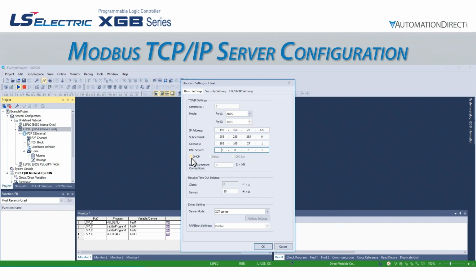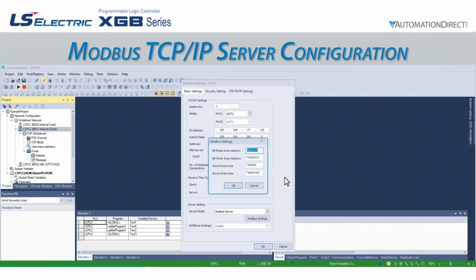If we are using the PLC as a Modbus server, we can go to the Server Mode dropdown and set it to Modbus Server. We also use the Number of Dedicated Connections field to set the number of connections that will be reserved for external Modbus clients with our PLC acting as the server. We will leave this at the default of 3. We can then click the Modbus Settings button, and the Modbus Settings window will open. In this window, we can configure the starting addresses that can be accessed for bit and word, read and write information from an external Modbus client.